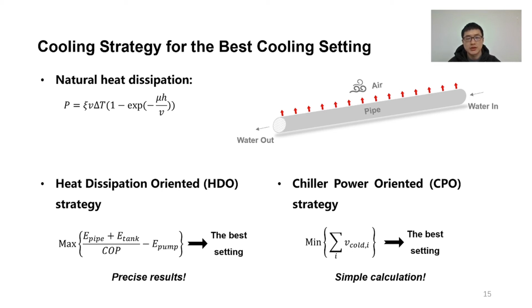Although the HDO strategy provides precise cooling settings, it could be infeasible if some parameters in the formula are inaccessible or varying dynamically. Therefore, we also develop a more practical chiller power-oriented strategy that calculates the cold water provision of all hardware components. By minimizing the total cold water provision, it can obtain the best cooling setting.